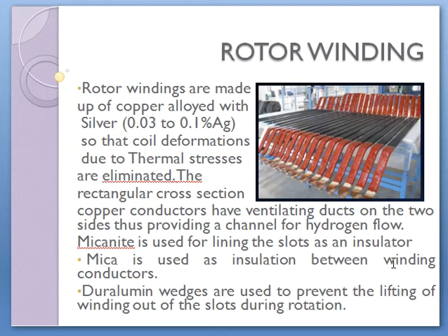Rotor windings are made up of copper alloyed with silver about 0.1% concentration, so that coil deformations due to thermal stresses are eliminated. The rectangular cross section copper conductors have ventilating ducts on the two sides, this side and this side, thus providing a channel for hydrogen flow for cooling purpose.